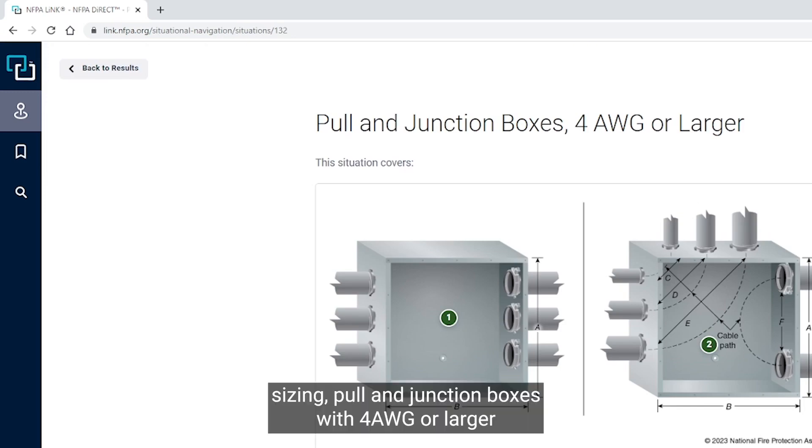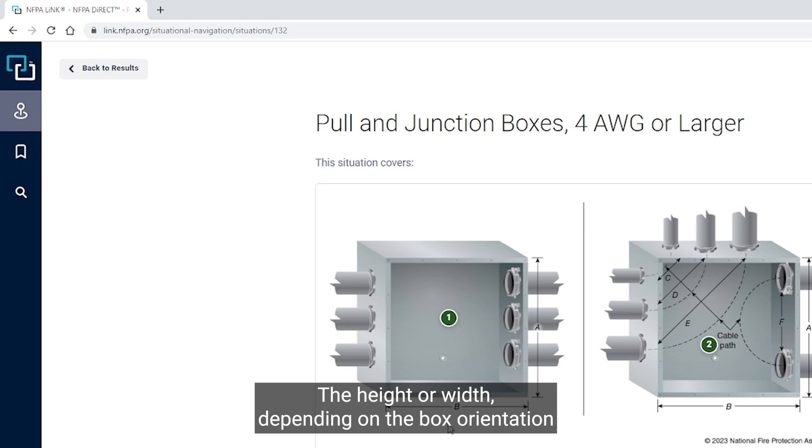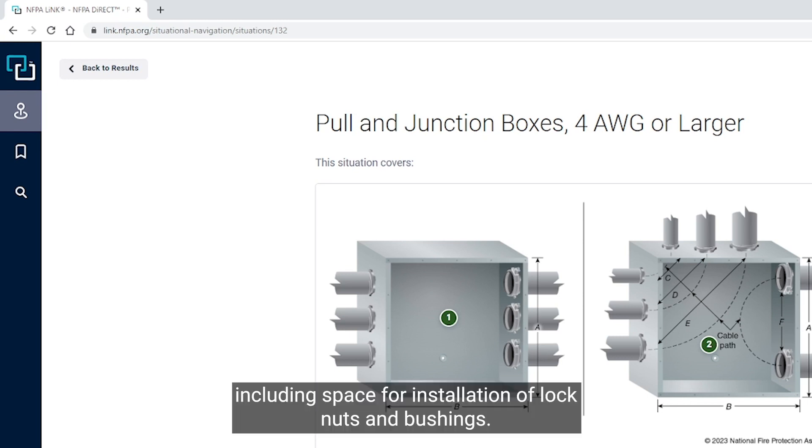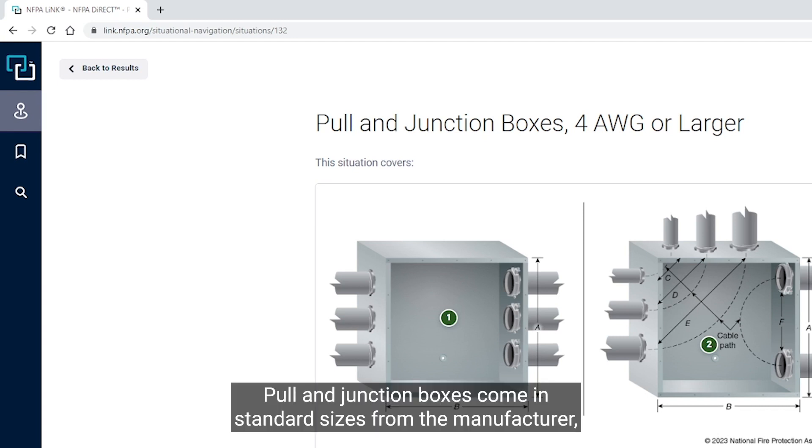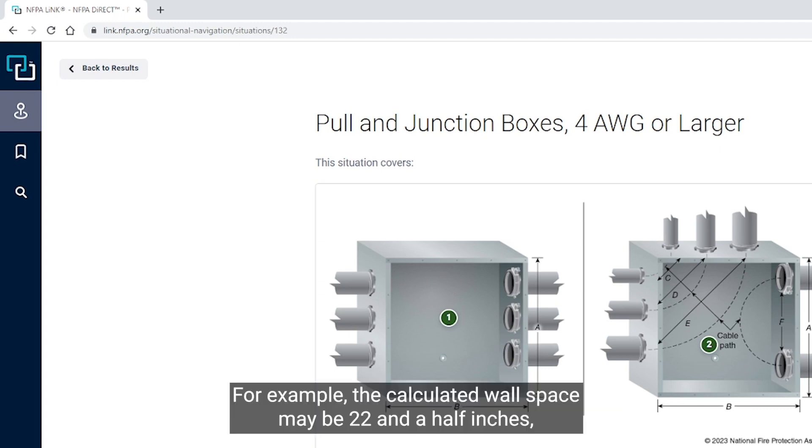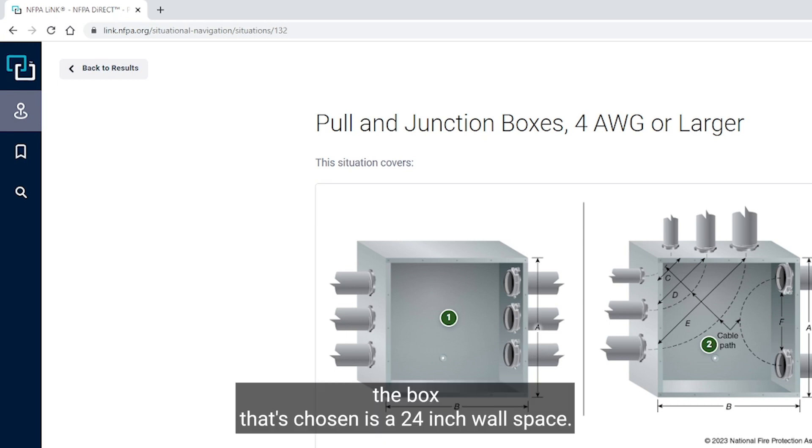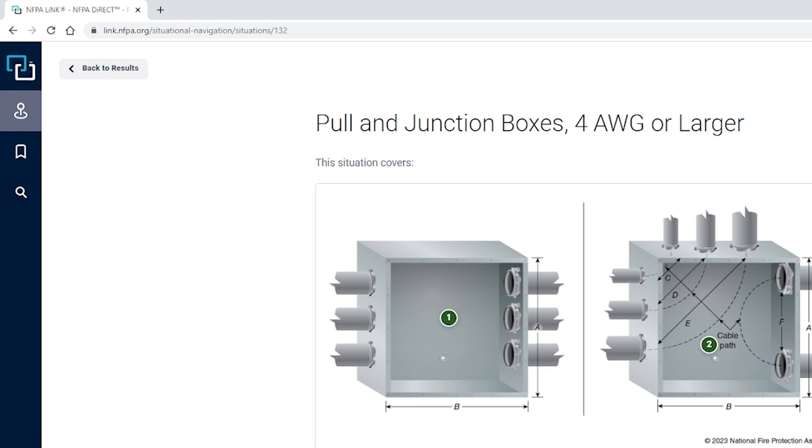Sizing pull and junction boxes with four AWG or larger conductors for a straight pull is, well, straightforward. The height or width, depending on the box orientation and the depth of the box, will be based on the overall raceway dimensions, including space for installation of lock nuts and bushings. Pull and junction boxes come in standard sizes from the manufacturer, which will ultimately dictate the size of the box.